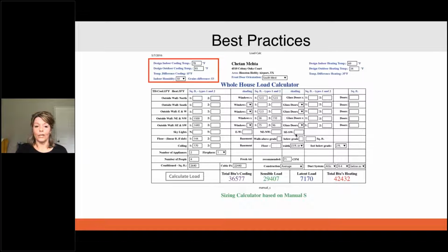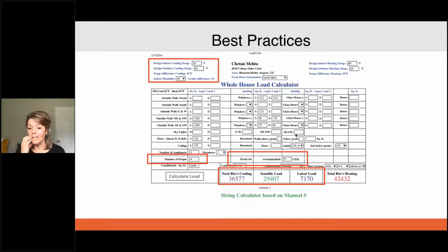So we're going to go through our design, how many people are in the house, how much fresh air ventilation I want, depending on what standard I'm using. And then it's going to tell me how many total BTUs of cooling based on sensible load and latent load. And the reality is most homes with our sensible and latent loads are becoming closer and closer in number. So we're not at that 29,000 for sensible versus 7,000 for latent. They're actually becoming quite a bit closer, which is challenging to design our AC systems for when they're basically designed to really focus on that sensible, that temperature load.